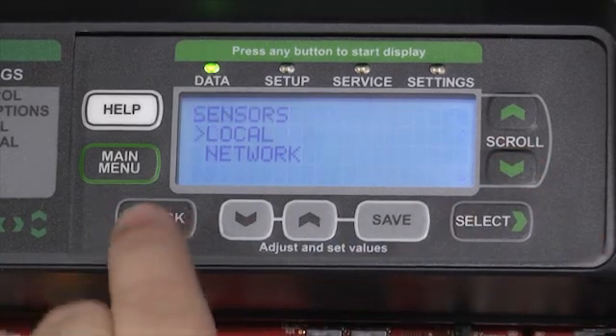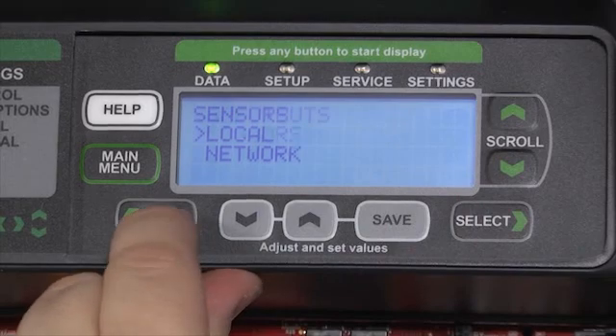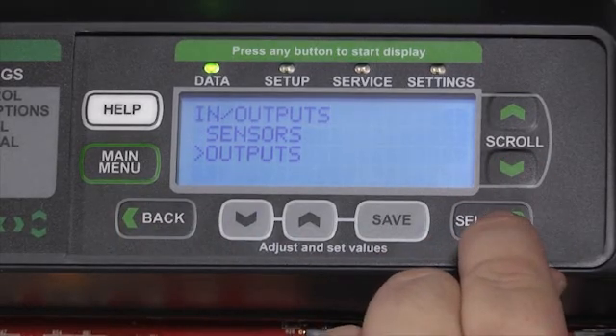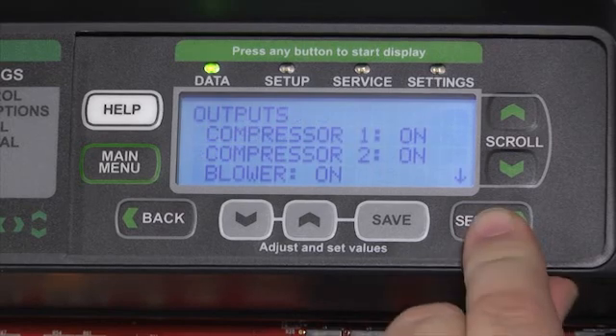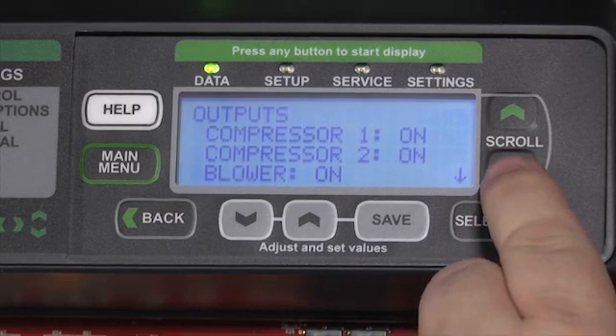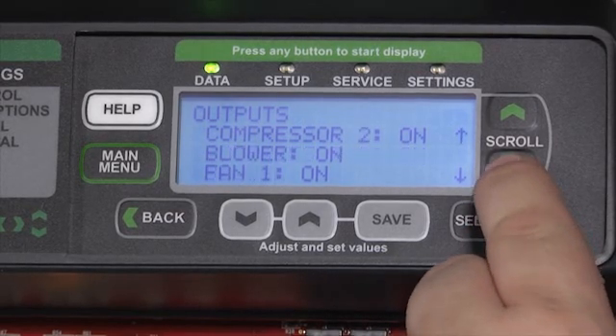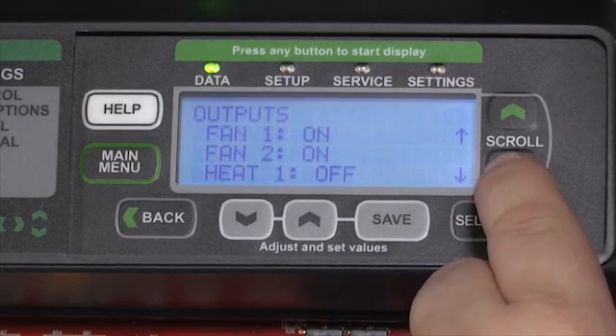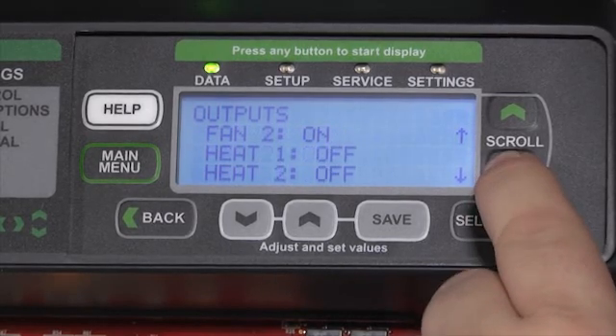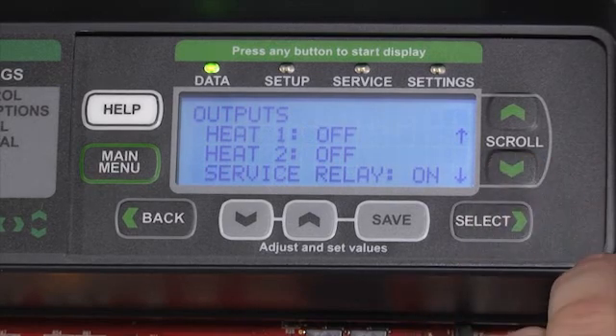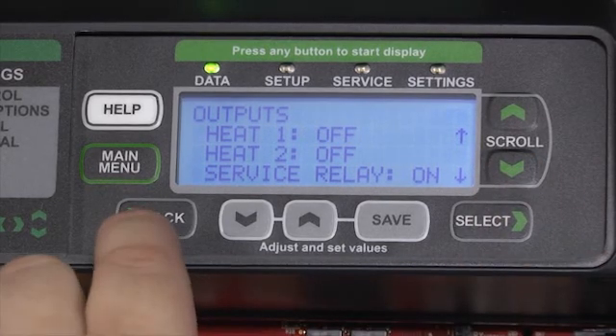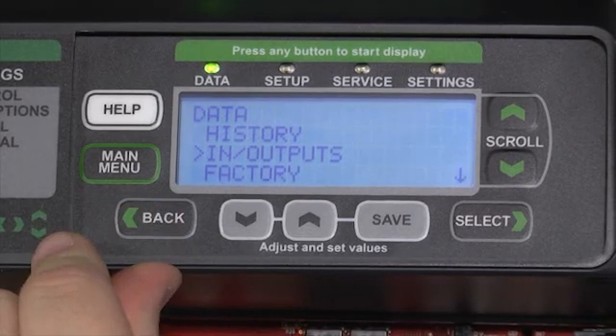The push of the back button will take us back, and we can then scroll down to the outputs, where with pushing the select button, we can now dive in and see what outputs are energized. For example, both our compressors are on, the blower is running, both fans are on, both stages of heating are turned off, and the service relay is in the on position. We can push the back button to navigate backwards through the modules, or we can hit the main menu to go directly back to the home screen.